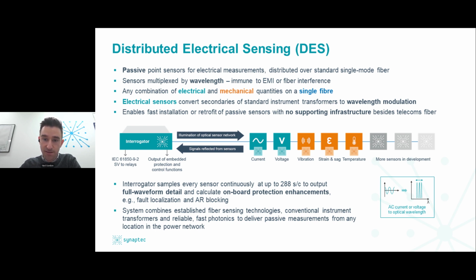So that interrogator, as you can see here, illuminates all the sensors in the array with a broadband light source, and the measured quantity from each sensor is encoded in the wavelength signal that's reflected back from each sensor. Now, because the measurements are multiplexed and encoded in optical wavelength, they're very robust to electrical interference, EMI, or fiber disturbance along the fiber run, and they can reach out very long distances because of that. Now, electrical sensing is our focus today, and the electrical sensors are connected to the secondaries of industry standard current and voltage transformers to passively convert the AC electrical quantity into a wavelength modulation. And that's what's measured locally at the interrogator. So those measurements are centralized and served by that interrogator, and the interrogator can sample all of the connected sensors simultaneously at up to 288 samples per cycle, and it can output the full IEC 61850 sampled value waveform and perform decisions with embedded protection and control functions as well.